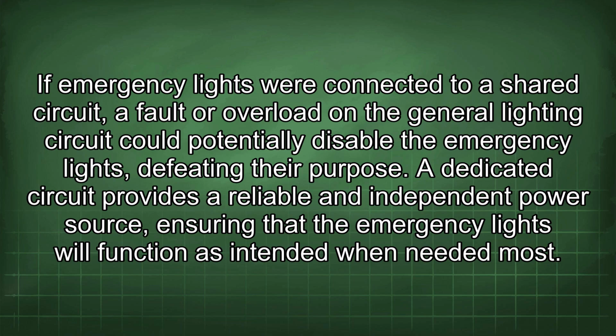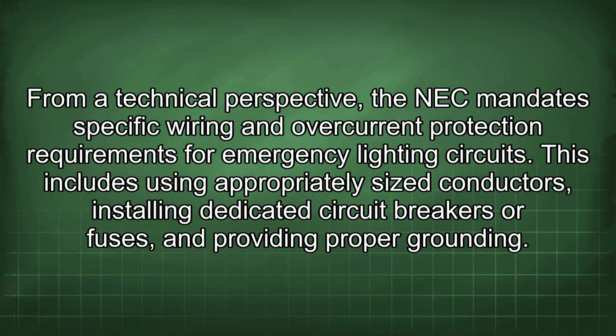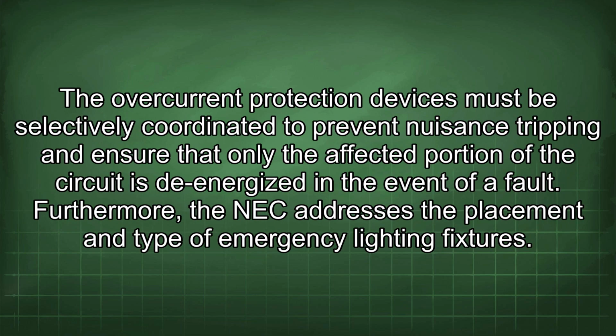needed most. From a technical perspective, the NEC mandates specific wiring and overcurrent protection requirements for emergency lighting circuits. This includes using appropriately sized conductors, installing dedicated circuit breakers or fuses, and providing proper grounding. The overcurrent protection devices must be selectively coordinated to prevent nuisance tripping and ensure that only the affected portion of the circuit is de-energized in the event of a fault.